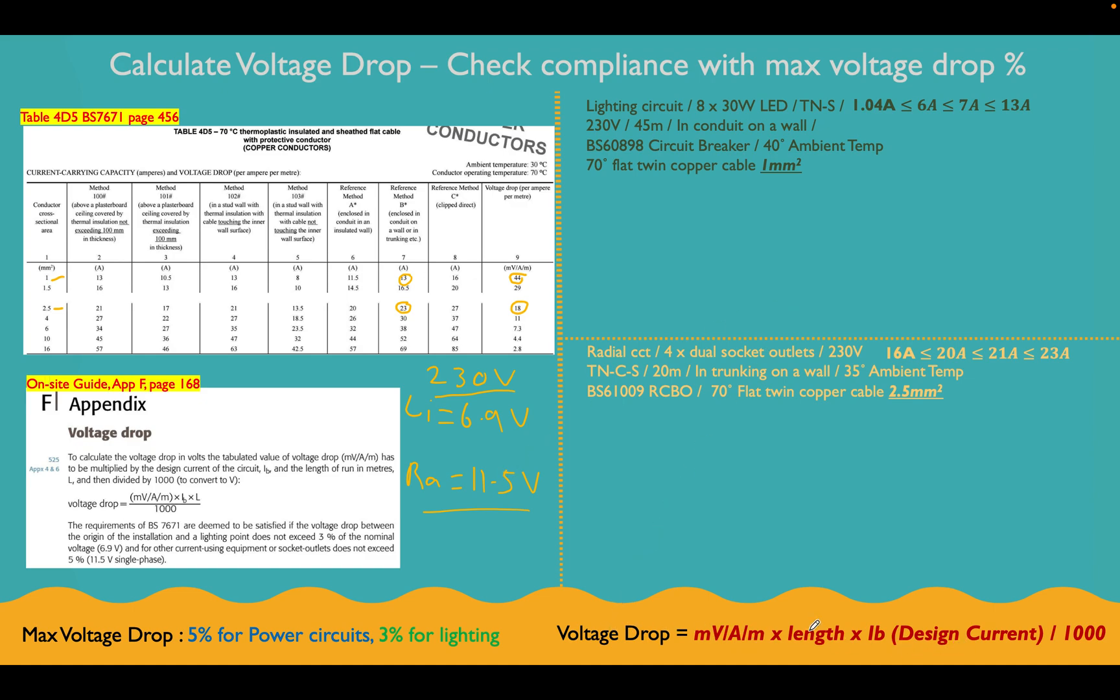So here's our formula, again, down here that we're going to go for. And then now, let's work our way through this. Let's go for it on this side. Let's do the lighting circuit first. So following our formula, let's find our little bits. So millivolt amps per meter for this circuit is going to be 44. Let's put that there, and we've got the length, which is equal to 45 meters. And then our design current for this circuit was 1.04 amps.